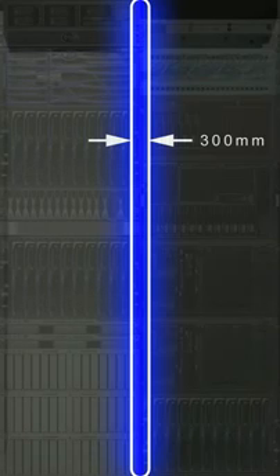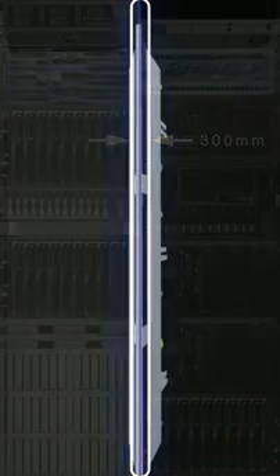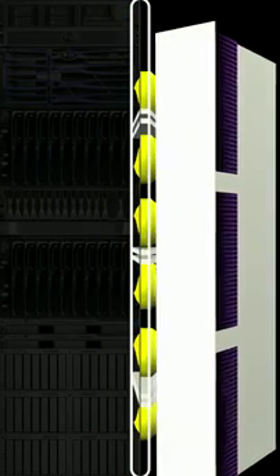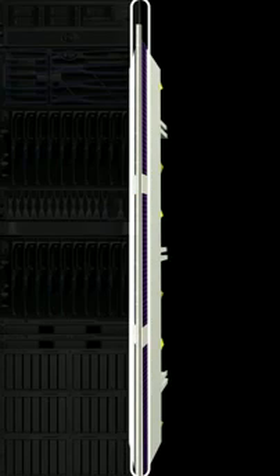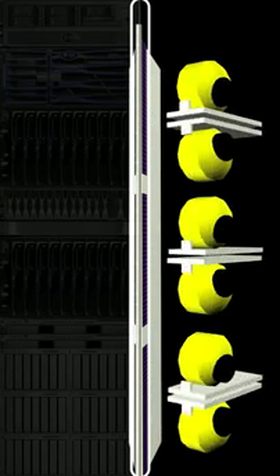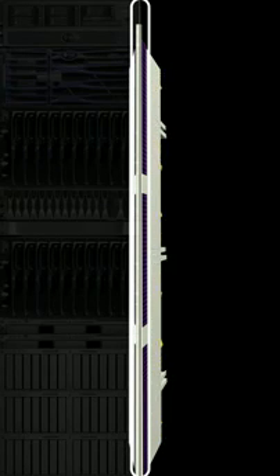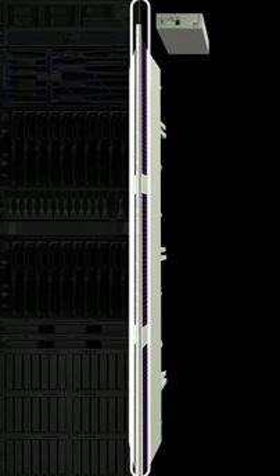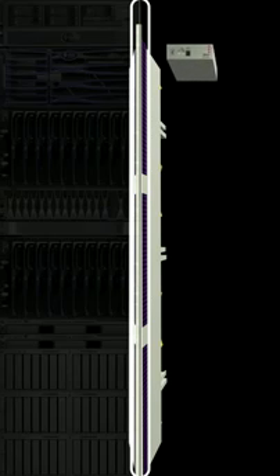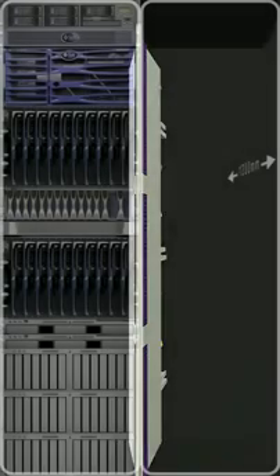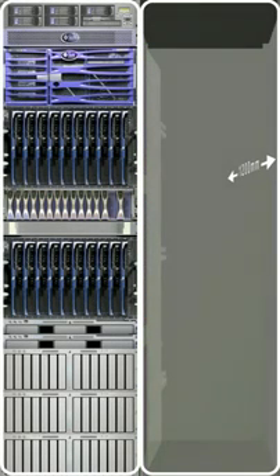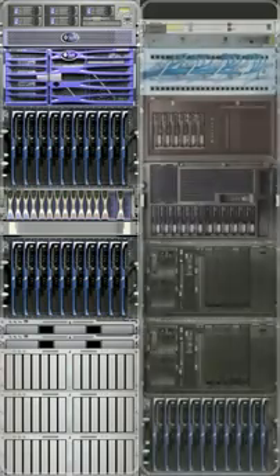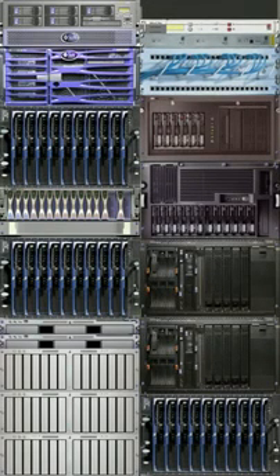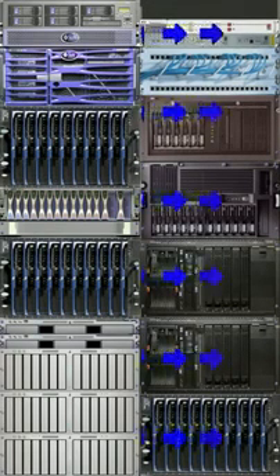The LCP Plus 300mm wide module consists of a heat exchanger fed from an external chiller system and 6 fans which circulate the hot air via the heat exchanger. Intelligent modules monitor the fans and the flow rates and are displayed on a touch-sensitive LCD screen on the front of the LCP Plus. The LCP Plus is connected to a standard 1200mm deep enclosure and pulls the hot air from the server exhaust and cools the air via the heat exchanger.